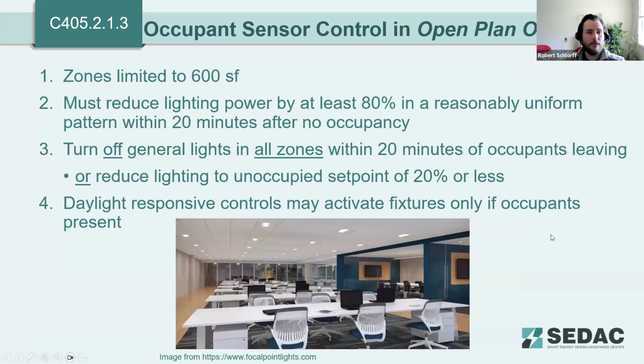Moving on to occupant sensor control within open plan offices. Now, these are open plan office areas that are greater than or equal to 300 square feet. The total lighting zones must be limited to 600 square feet total. The controls must reduce lighting power by at least 80% in a reasonably uniform pattern within 20 minutes after no occupancy. The controls must turn off general lights in all zones within 20 minutes of the occupant leaving, or you can reduce lighting to an unoccupied set point of 20% or less within 20 minutes of the occupant leaving.